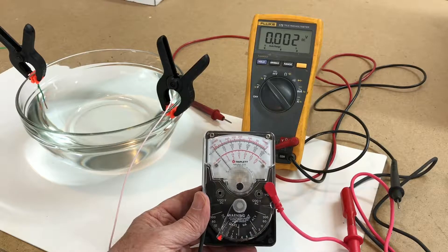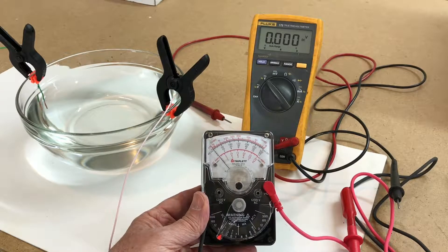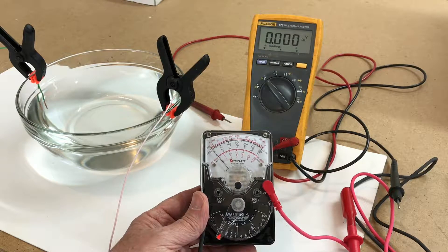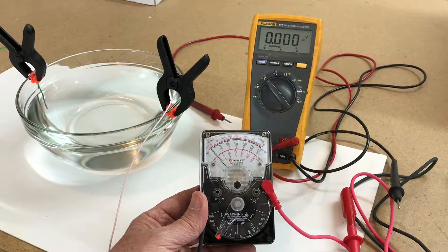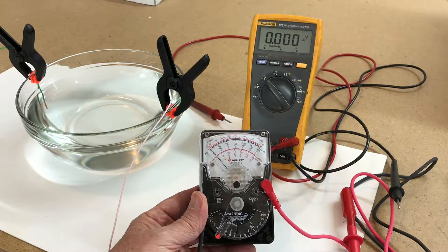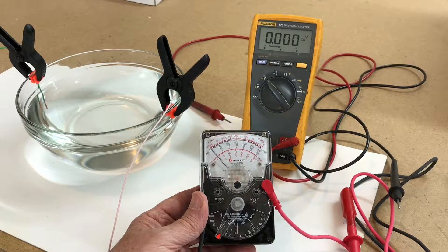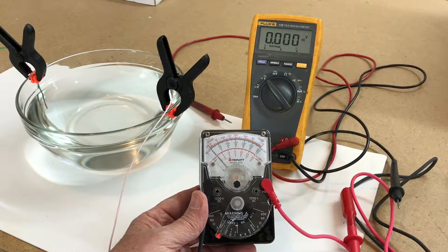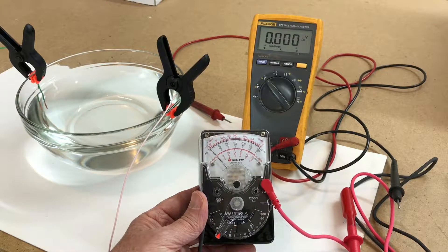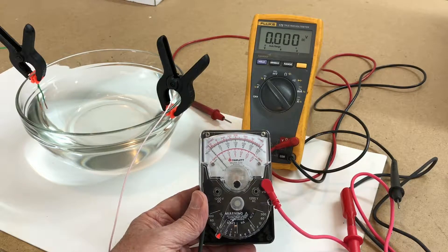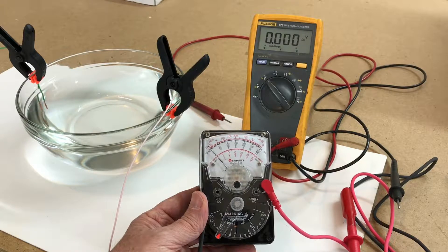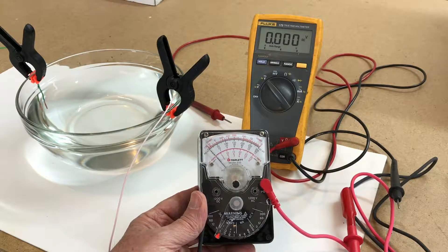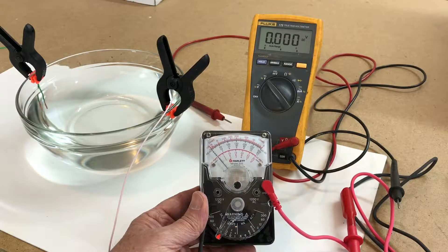If you try to use a Fluke or a digital meter to check for high resistance grounds, a lot of the times you won't see a ground on the digital meter. The panel sees the ground because of the voltage. Most fire alarm panels operate at 24 volts DC, and when you apply 24 volts DC to the circuit that's grounded it breaks down to ground and the panel sees it, but the Fluke doesn't put out enough voltage on continuity to break the fault down.